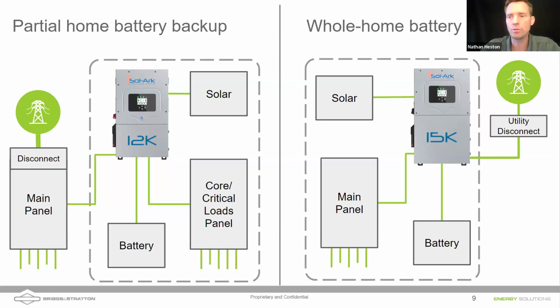So in a grid-down situation, yes, you're disconnected from the utility so that we're not backfeeding, maybe from our solar, but now we're still backing up the entire house. So two different options there, and the installation is a bit different - run times are obviously different if we're not backing up the whole home. Load management can be done, and even on the Sol-Ark, if you're not using a generator, you can use that generator port on the Sol-Ark 15K to actually run a sub panel where you could do managed loads.